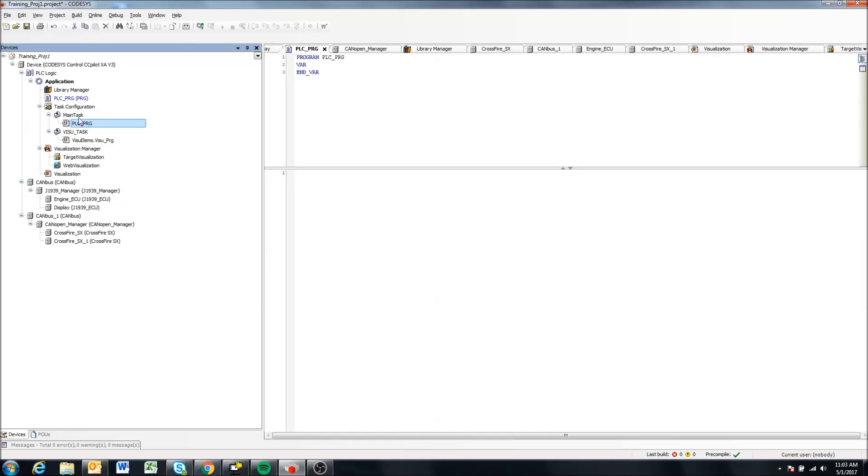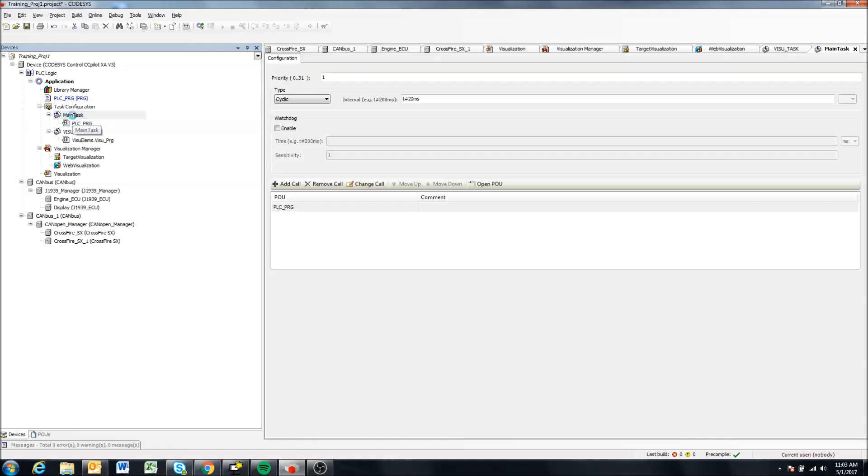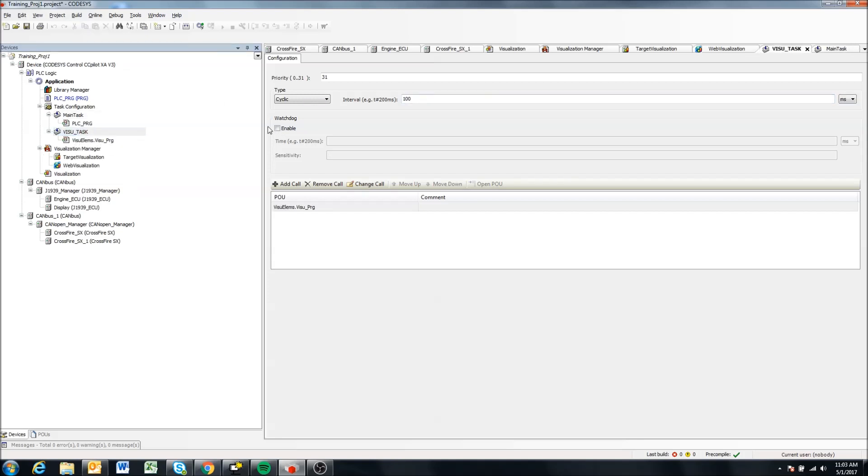So your main PLC PRG task is going to be updated every or looped every 20 milliseconds. Here we're updating the visualization task every 100 milliseconds. So again, it doesn't need to be any faster than this normally, but you may want to slow it down.